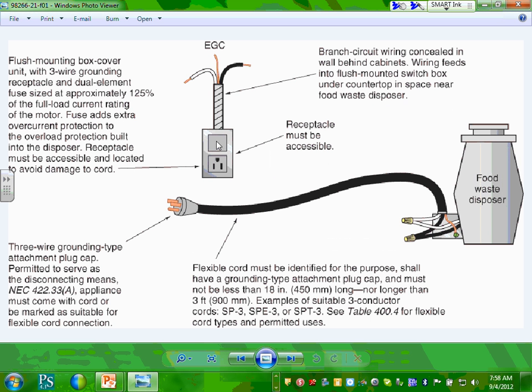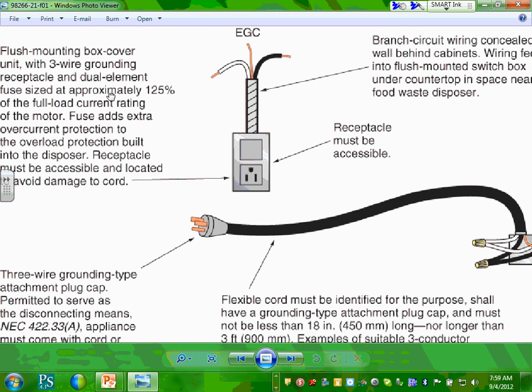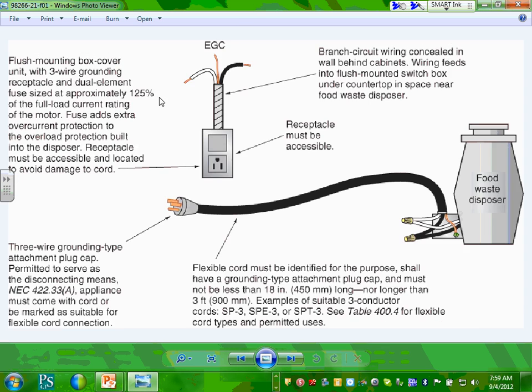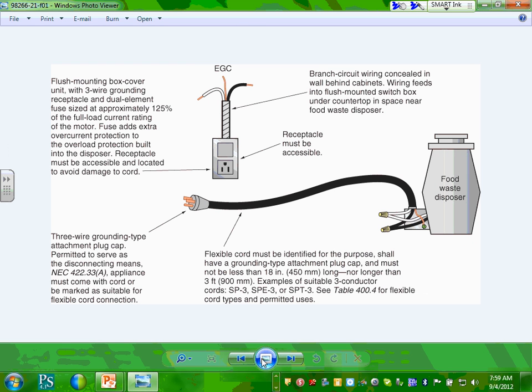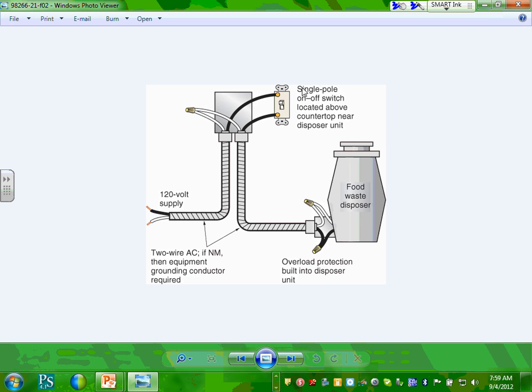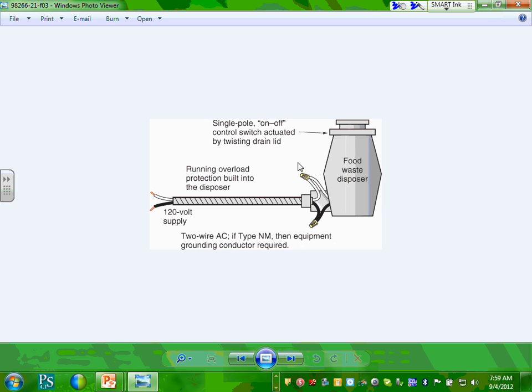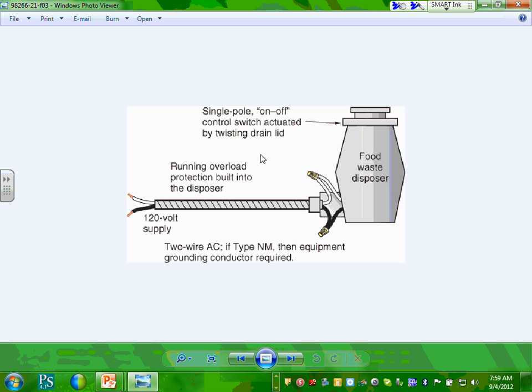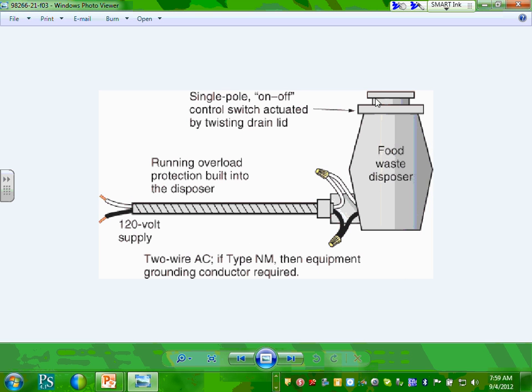Branch circuit coming to a receptacle. Sometimes we fuse the receptacle. When we size the conductors, we size them based on 125%. I showed you guys how to size that one. Any comments, any questions? Here's where you hardwire that one. Same thing, hardwired. This one they call a control switch, actuated by twisting the drain lid. So in this case you don't need a switch to control it, but you still need a plug or a switch as a disconnect.